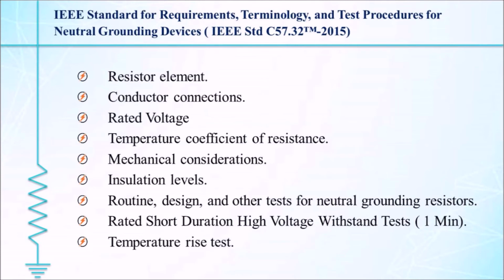Fifth, mechanical consideration. Resistors should be designed to facilitate lifting and should be provided with lifting eyes or similar devices to allow safe, rapid installation. Lifting and handling instructions should be clear and readily available. Sixth, insulation level. The line end and the ground end insulation level shall be selected on the basis of fault voltage criteria.